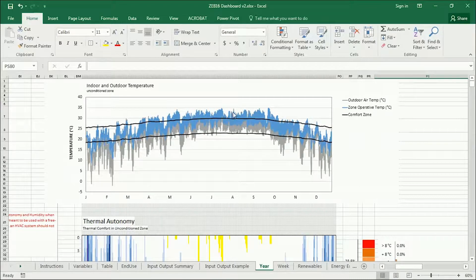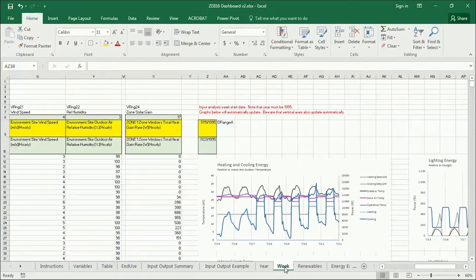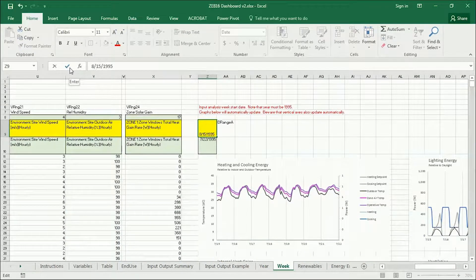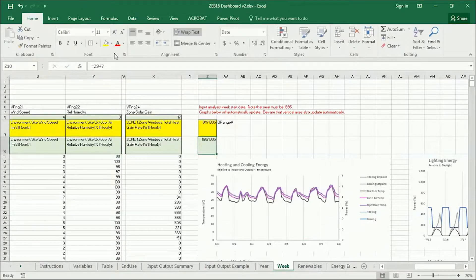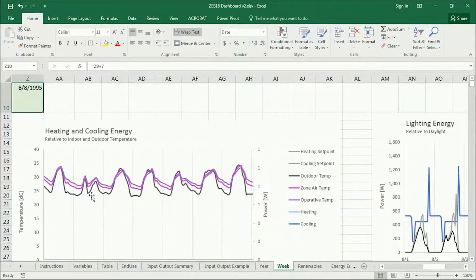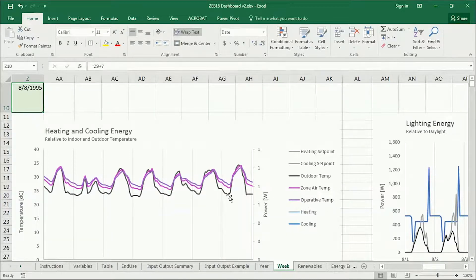Let's look at that week — it looks like about the first week in August. So we go to the Week tab and type in August 1st. This graph here shows the black line as the outdoor temperature, the pink line as the air temperature — that's the zone air temperature — and the purple line is the operative temperature, which includes the surfaces around it. Operative temperatures are staying a little bit warmer than the mean air temperature.